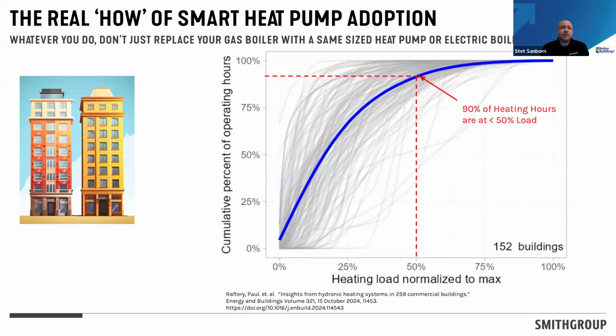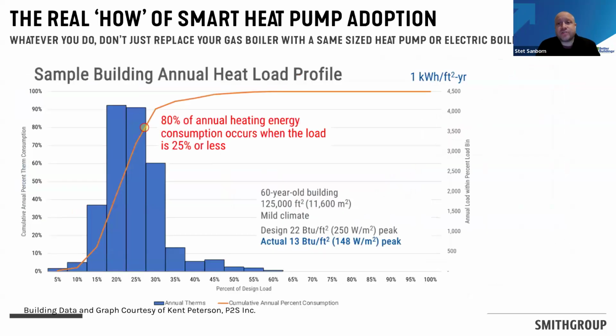This is similar data from another campus project my colleague Kent Peterson at P2S did as part of their survey work. In a probably milder climate than the first data set, 80% of hours were at less than 25% of the load. As Jess mentioned earlier, it was cheap to put in an oversized boiler in these existing buildings—it is not cheap to put in an oversized heat pump.